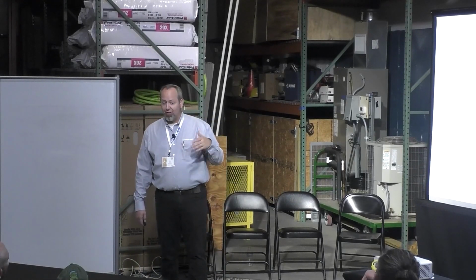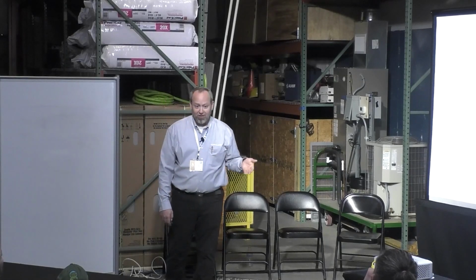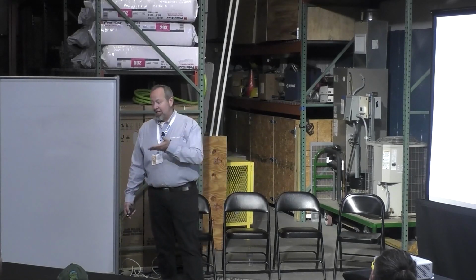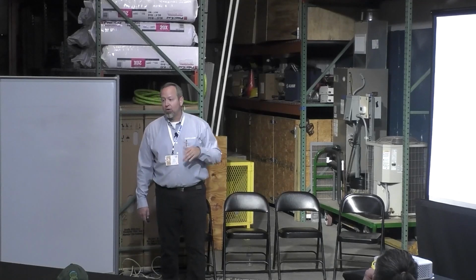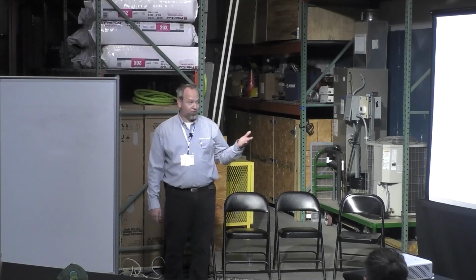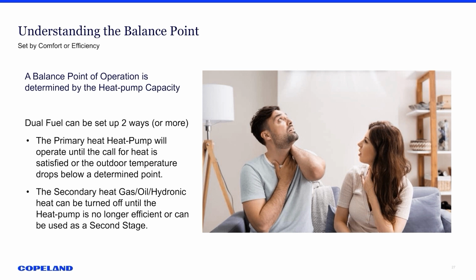So you can have your heat pump basically running 24/7, which is fine if it's creating comfort for the homeowner and it's not drafty for them. If it's drafty for them, then you may want to consider a balance point at which you do shut that second stage or that primary off and make the second stage the first stage.